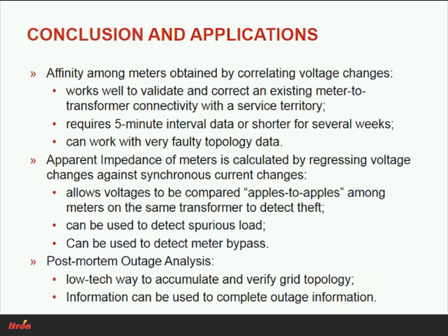The issue there is that the meters will experience the same voltage unless, of course, the unmetered load happens along a lateral, so some meters are downstream and some are upstream from that lateral. We actually do correct for that by looking at a long-term bias.